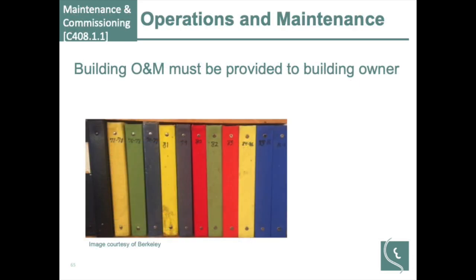And it now requires the building owner manual to be provided to the building owner. Previously, it wasn't part of the code. The usability of this is what's in question. I know I've been in facilities with shelves and shelves and shelves of owner manuals and install manuals, and they've got 3 inches of dust on them. It's one of those things where they're trying to get people to start using those to maintain their facilities better and maintain long-term efficiency. But the client actually has to do it themselves. So the code is trying to facilitate that through the requirement that those materials be provided to the client.